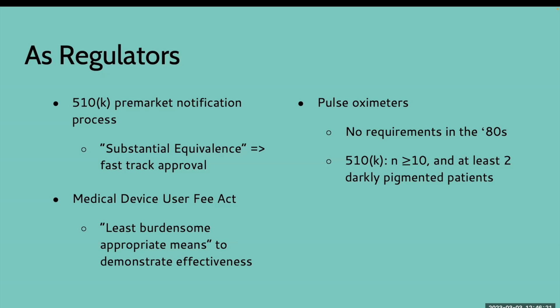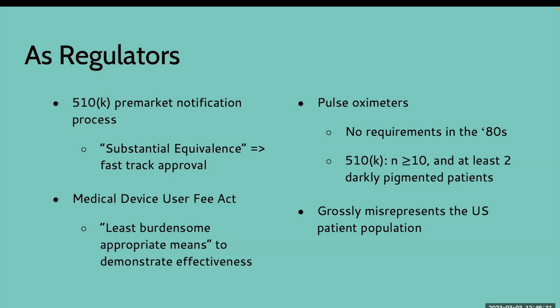What did this look like for pulse oximeters? Well, in the 80s, the first oximeters had no requirements for gender and racial diversity. And after being adopted from a Japanese study, they were tested in the US almost exclusively on white male patients. Following the creation of the 510(k) clearance pathway, only 10 participants were required to demonstrate efficacy, and it had to include at least 2 darkly pigmented individuals for testing. This grossly misrepresents the US patient population.